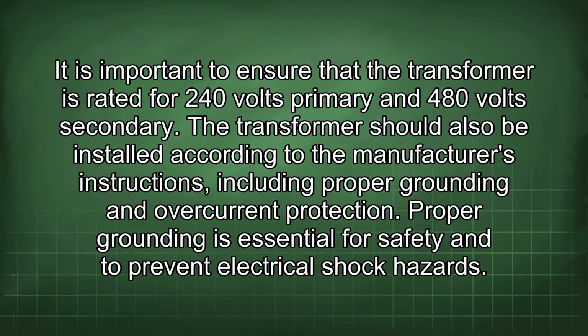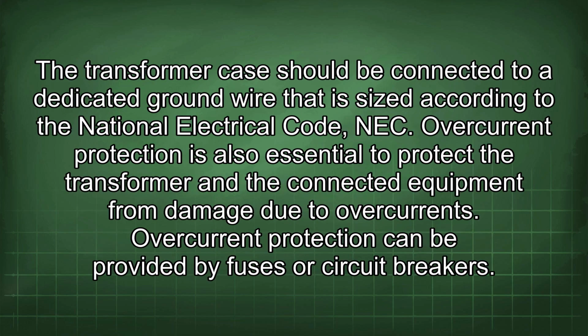It is important to ensure that the transformer is rated for 240 volts primary and 480 volts secondary. The transformer should also be installed according to the manufacturer's instructions, including proper grounding and overcurrent protection. Proper grounding is essential for safety and to prevent electrical shock hazards. The transformer case should be connected to a dedicated ground wire that is sized according to the National Electrical Code (NEC).